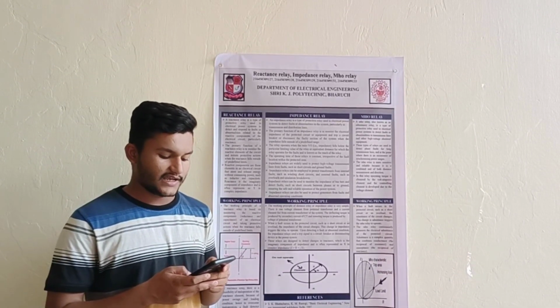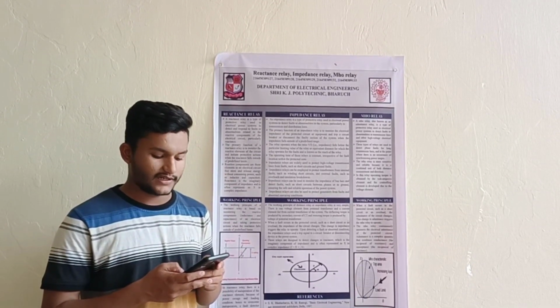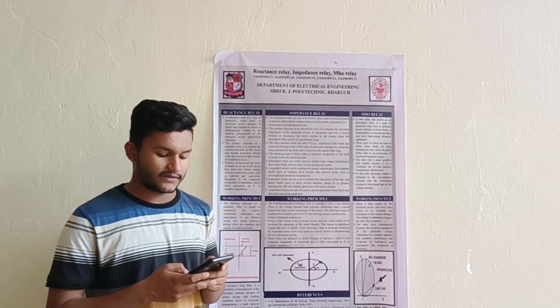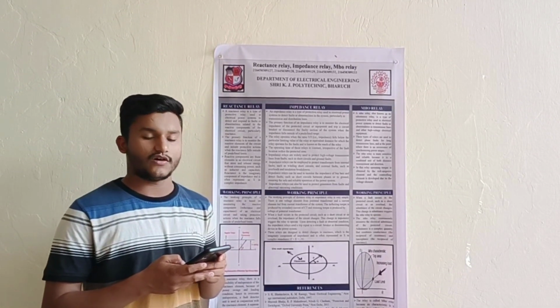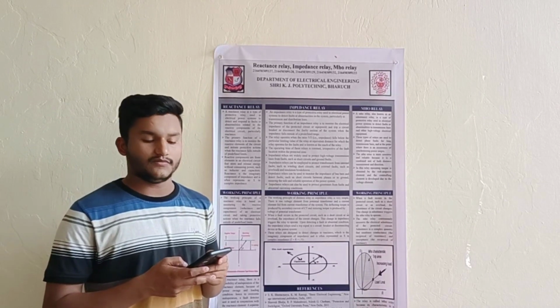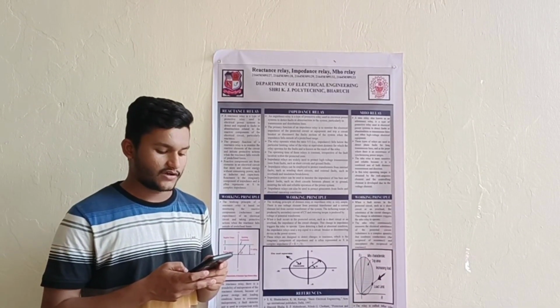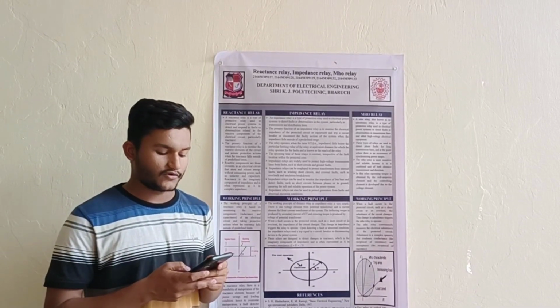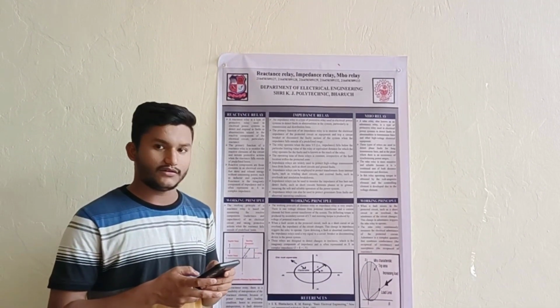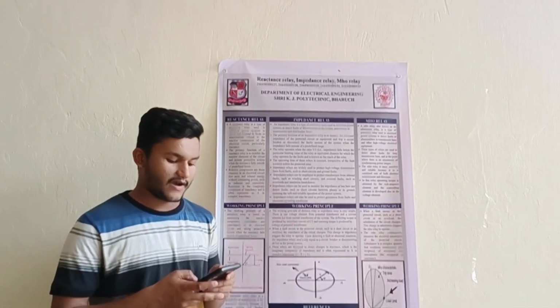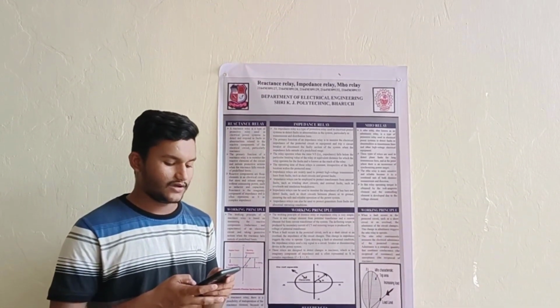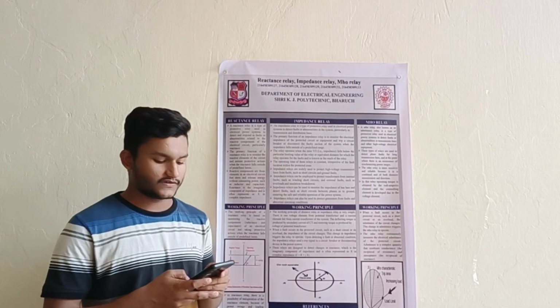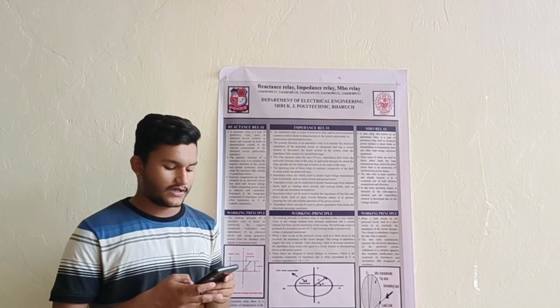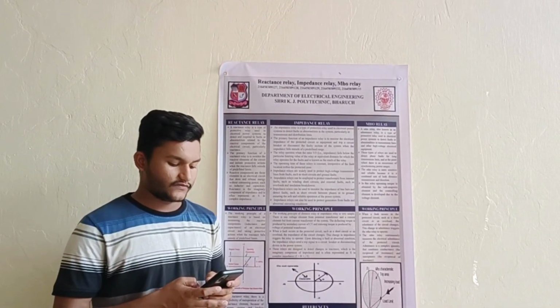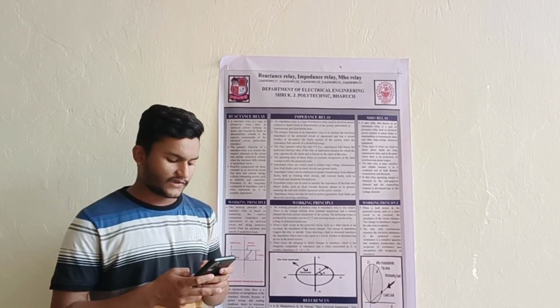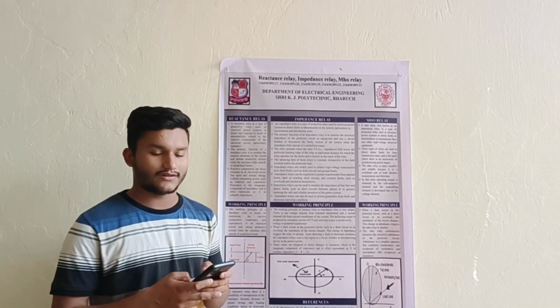This helps in quickly isolating the faulty section and minimizing disruption to the rest of the power system. Fault location. Impedance relays can also be used for fault location purposes by measuring the impedance at different points in the power system and comparing the values. The relay can determine the approximate location of the fault. This information is useful for maintenance crews to quickly identify and repair the fault.